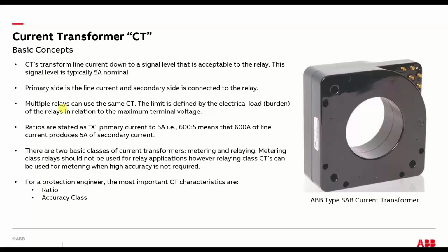The limit is defined by how much physical load that CT can drive, and that is relative to the accuracy class of the CT. And that gets a little complicated, but the larger that class is, and it's usually a C something, like C100 or C200 or C50, that C accuracy class is basically equivalent to how much electrical load the CT can drive and remain accurate, remain out of saturation. It's sort of like terminal voltage. So if you have a C100, well, I think I have an example here.